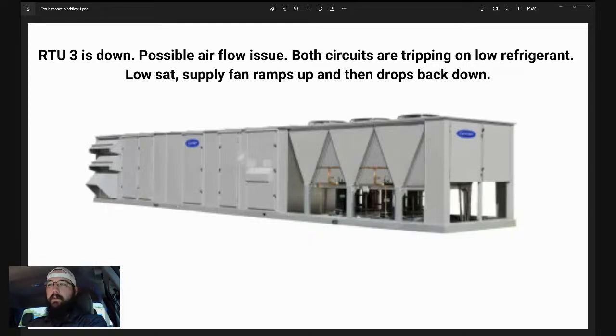I mean, to an extent, there are limitations, but the point is, he decides, and if something's not working, he can fix it. Whereas in our case, our control board is a locked-down PLC. It is a device that the manufacturer writes their program for. And when we run into these types of scenarios where things aren't lining up, we have to start thinking about what the logic of the unit is doing that would make it do this.